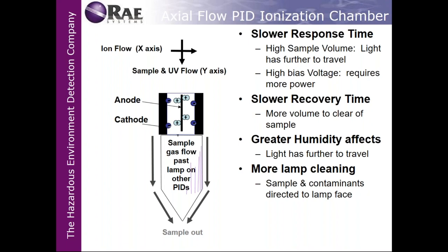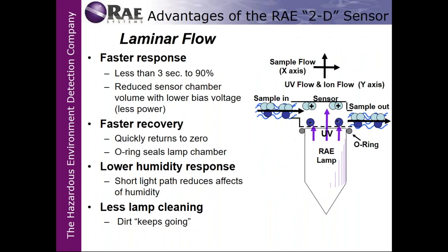The plus or minus error rate for a PID sample back in the day was as high as 30%. Now we've narrowed it down to under 10%. So the laminar flow gives a faster response, less than 3.0 seconds to a T90, or 90%. Reduced sensor chamber volume with low bias voltage requires less power. Faster recovery, we talked about that in the last slide.